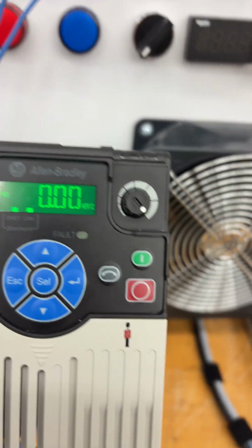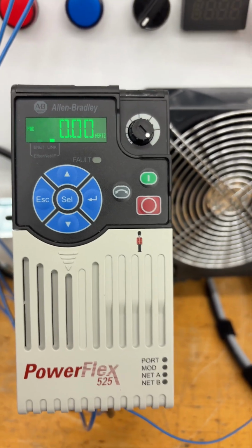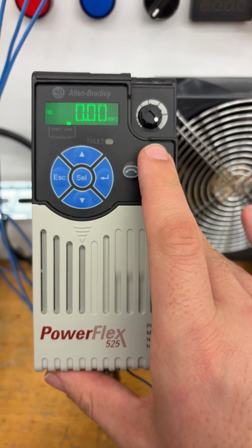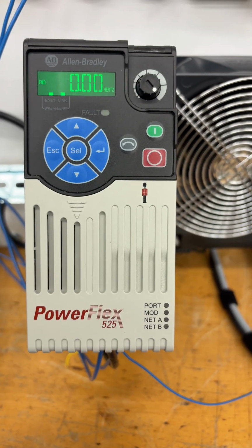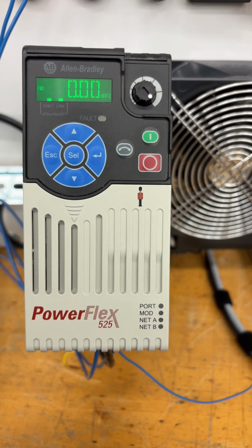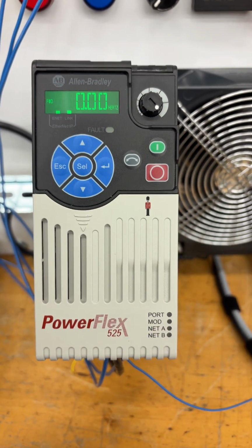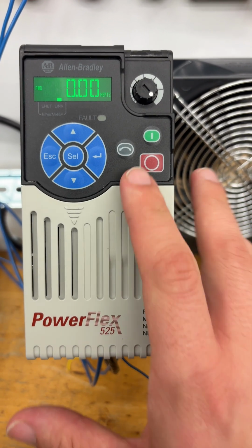This time I'm going to talk to you about how to add S-curve to your variable frequency drive parameters. So in order to understand what S-curve is, I first want to demonstrate the frequency drive ramping up and ramping down with no S-curve. So this is going to be a linear acceleration from the minimum, which is 0 hertz, to the maximum of 60 hertz across 10 seconds. Then when I hit the stop button, it's going to do a linear deceleration from 60 hertz down to 0.